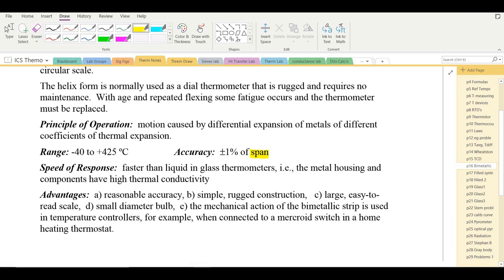Response speed is faster than liquid-in-glass thermometers because the metal housing and components have high thermal conductivity. Advantages include reasonable accuracy, simple rugged construction, large easy-to-read scales, and small diameter bulb, meaning the thermometer's mass should not significantly affect the sample temperature.